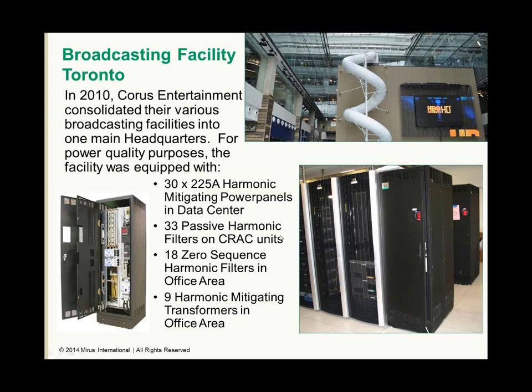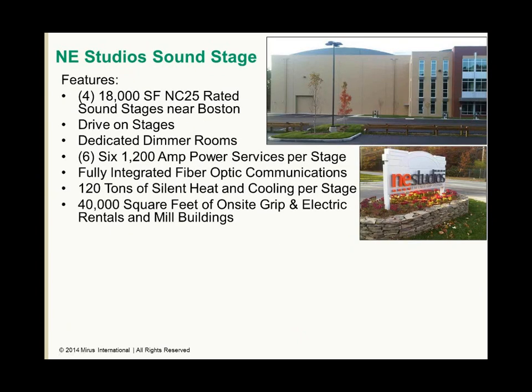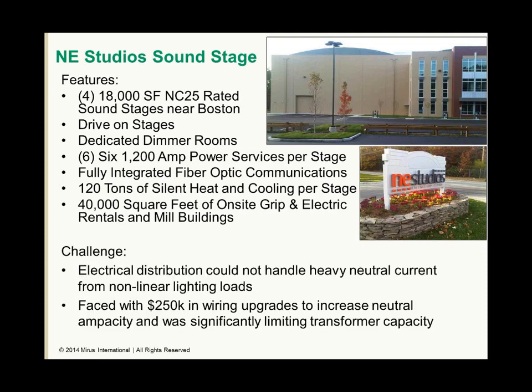Recently, we discovered another application for our products in the film industry. A new sound stage built by New England Studios near Boston discovered that their electrical distribution system would not be able to handle the high levels of neutral current from nonlinear lighting and dimming systems. They faced a $250,000 upgrade of their wiring to increase neutral capacity, and were being significantly limited on their transformer capacity.